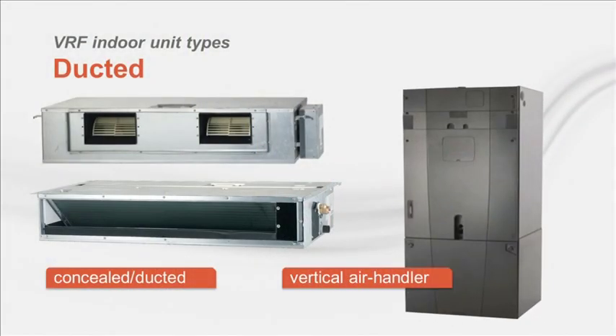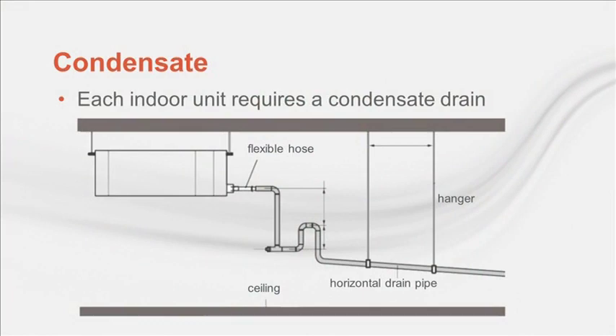Finally, some VRF systems are even installed with residential-style air handlers, installed either horizontally or vertically. Common applications include retrofit projects with available closet, attic, or equipment room space. Each of these VRF indoor units uses an electronic expansion valve to maintain suction temperature and comfort. And of course, the indoor units serve as evaporators in the cooling mode, which results in the formation of condensate on the coil that must be managed. So they commonly include either an integral or field-installed condensate pump. Each VRF indoor unit needs to be individually piped to a condensate drain or disposal system.